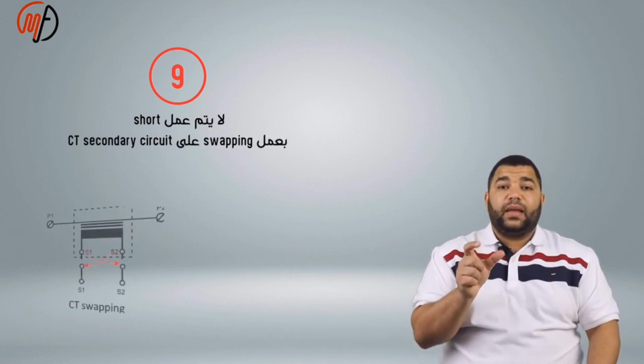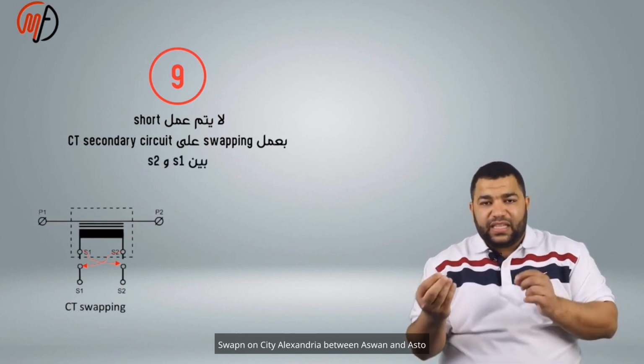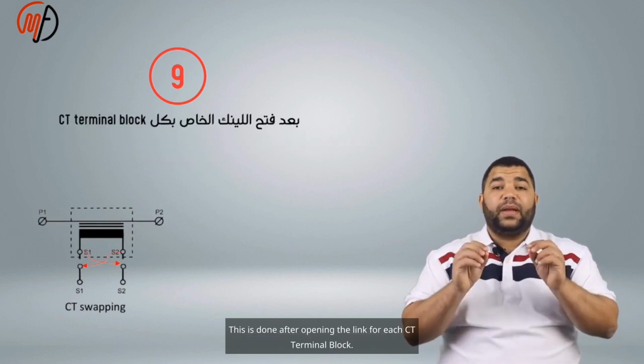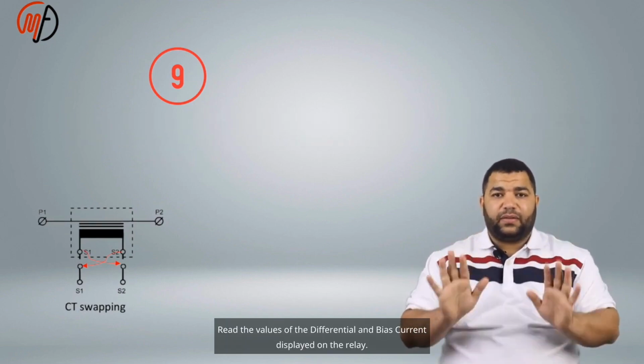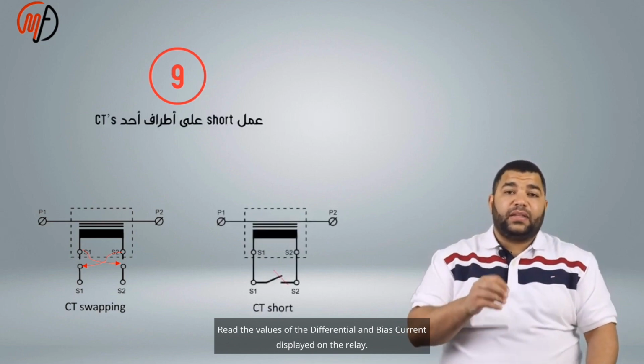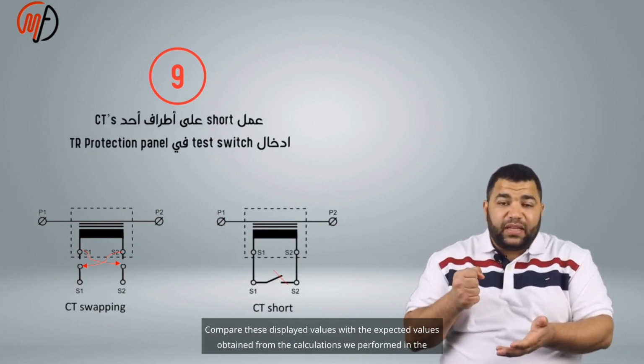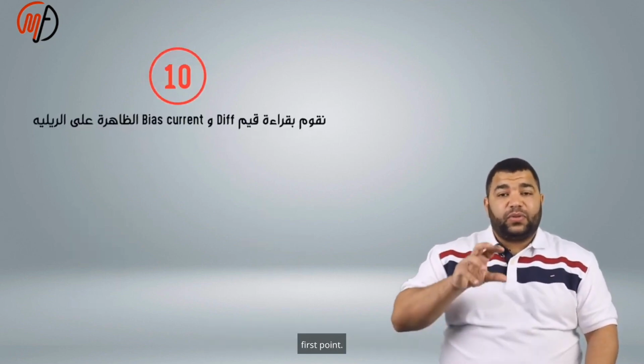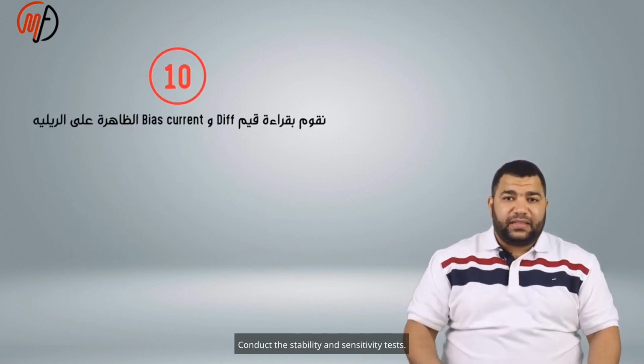Swapping the CT connections between S1 and S2 is done after opening the link for each CT terminal block. Read the values of the differential and bias current displayed on the relay. Compare these displayed values with the expected values obtained from the calculations we performed in the first point. Conduct the stability and sensitivity test.